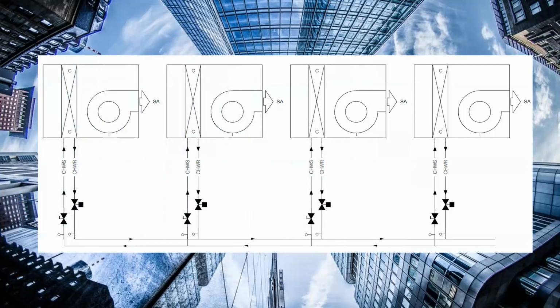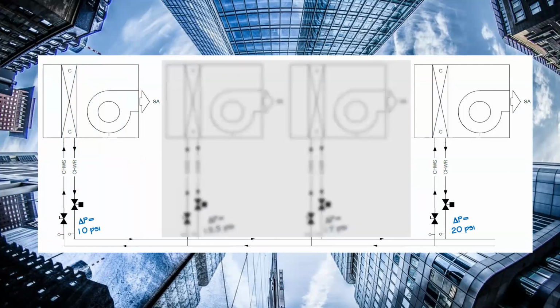Here we see those 4 piped together, but since this is a direct return system, we know the far zone will have a relatively low pressure drop, and in this case, it's going to be 10. And each zone, as we get closer to the water source, will have an increasingly higher delta P. In this example, let's just look at the 2 extremes. The far zone at full flow, far from the pump, the coil will take its design pressure drop, in this case 4 psi, and the valve was sized for that 4-pound pressure drop. This leaves 6 psi for the balancing valve to consume. So we have a valve authority of 4/10 or 0.4, which is 40%.